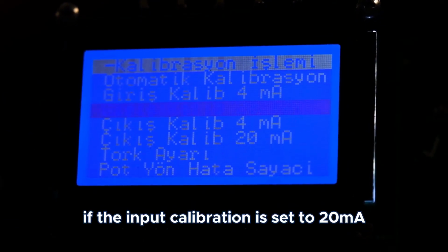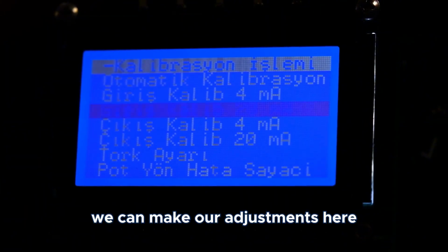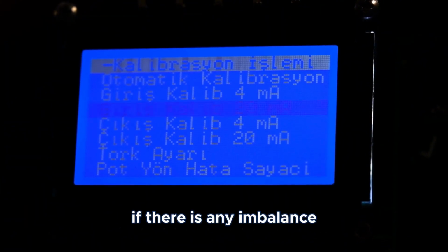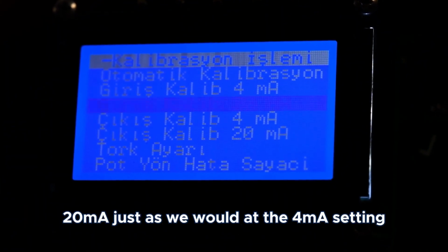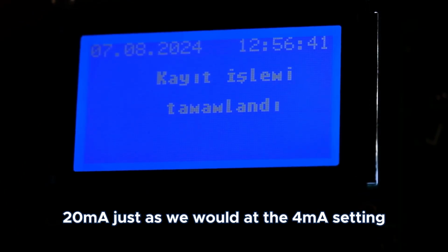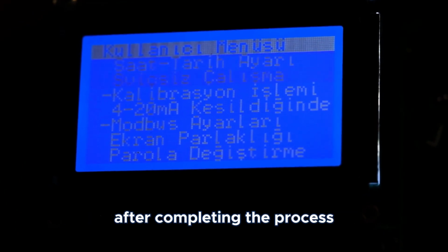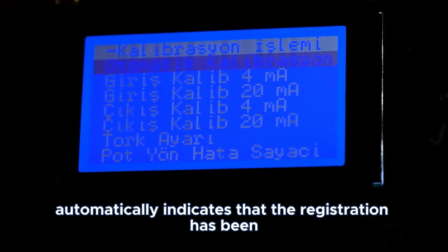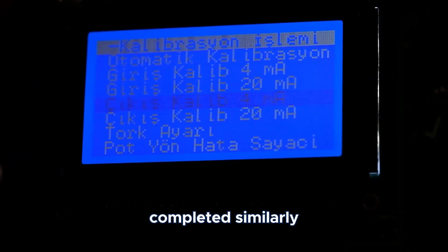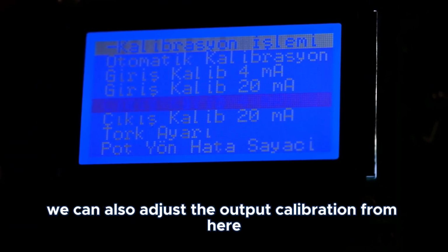If the input calibration is set to 20 mA, we can make our adjustments here if there is any imbalance or malfunction in the incoming 20 mA, just as we would at the 4 mA setting. After completing the process, it automatically indicates that the registration has been completed. Similarly, we can also adjust the output calibration from here.